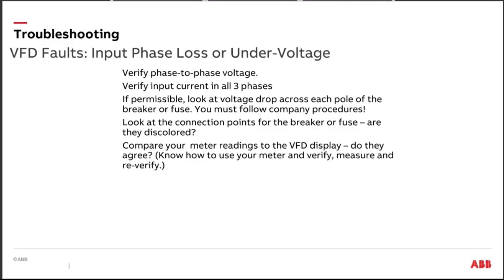Have a meter, know how to use your meter, check your meter, verify your meter. Verify, measure, and verify, okay? Three times. Let's look and see what it says. One more time here. If you're the person in the field, remember, breakers don't have a top and bottom. There's not an input and output side. A breaker can be top fed or it can be bottom fed. Be aware of that. Be cognizant of that, okay?